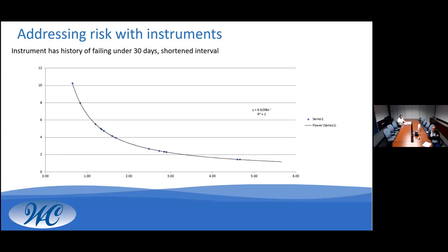So this is a problematic instrument and it has a history of failing under 30 days. So when it was assigned to a 30-day calibration interval, when we would get it back at the next 30 days, we would find it out of calibration almost all of the time. So problematic instruments with a high risk of being thrown out of calibration impact the validity of our data.